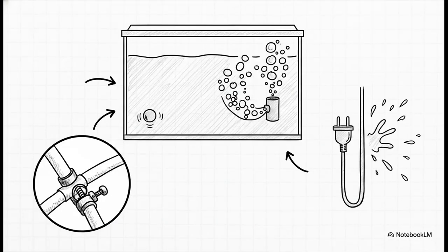But here's the catch. Even the absolute best hardware with all those safety features is going to fail if it's installed poorly. Proper placement is just as important as the features themselves. You have to mount your sensors where they won't be bombarded by bubbles or weird currents. Make sure your tubing connections are completely secure to prevent leaks. And just use common sense to route all your power cables safely away from splash zones.